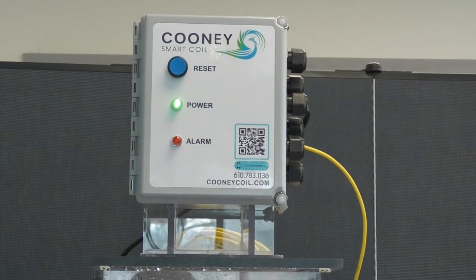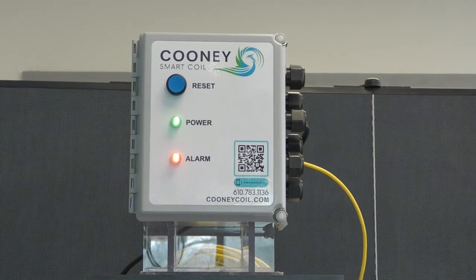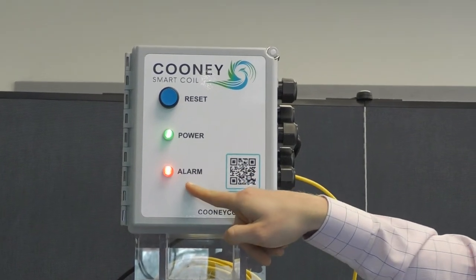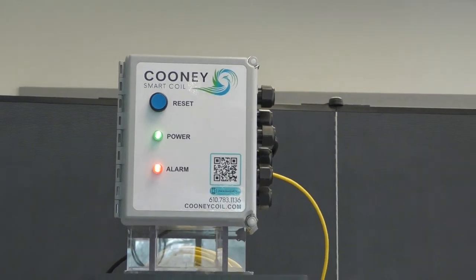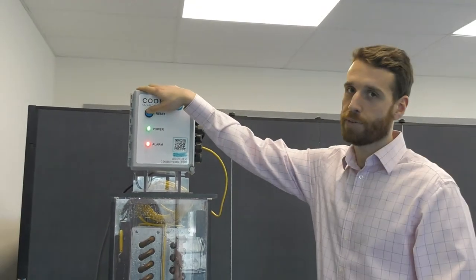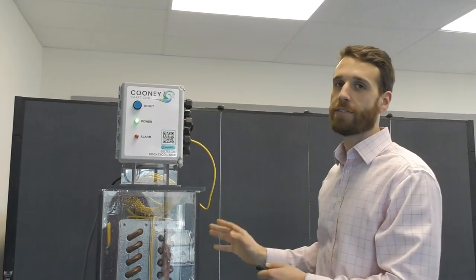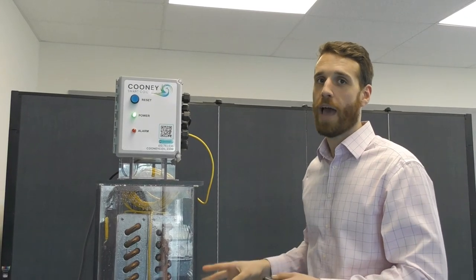When the coil freezes, the system will go into alarm, the BMS is notified, and the system needs to be manually reset so that somebody can put their eyes on the situation and know what's happening.